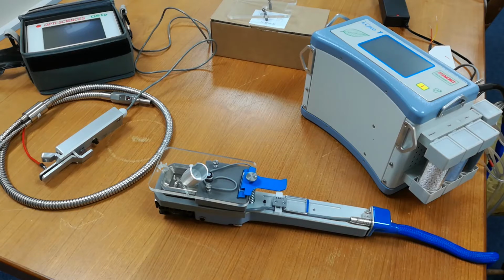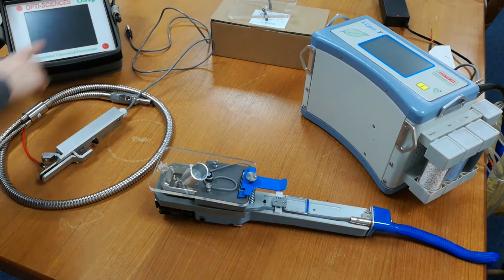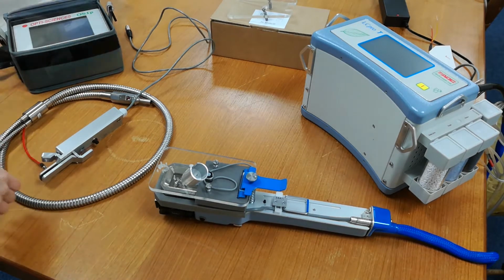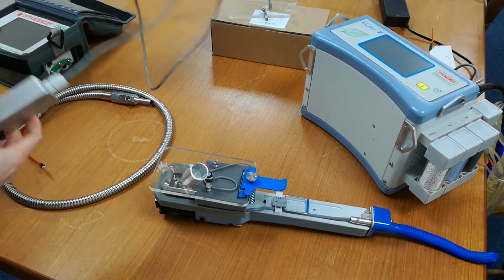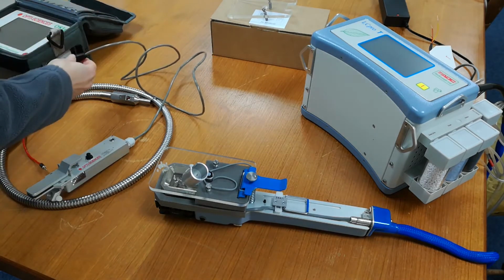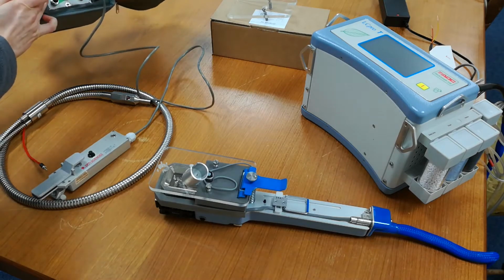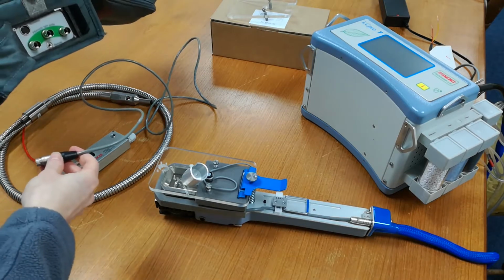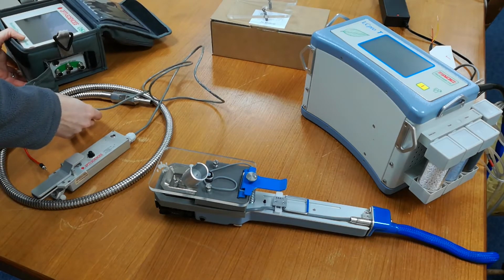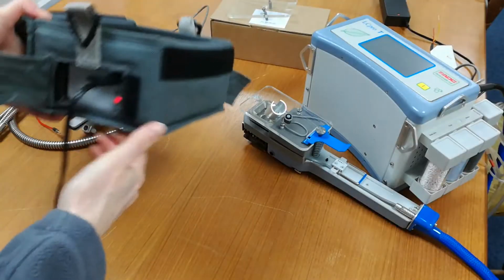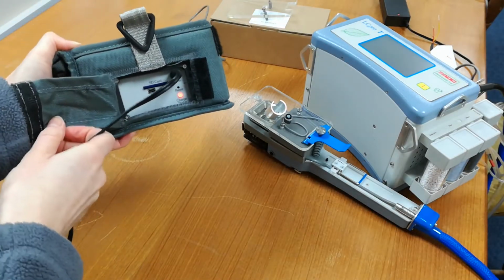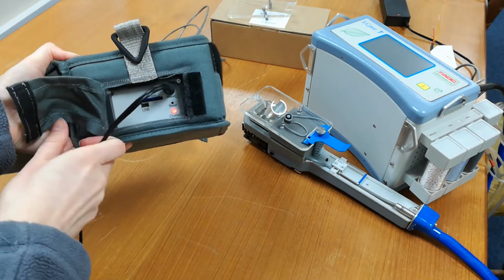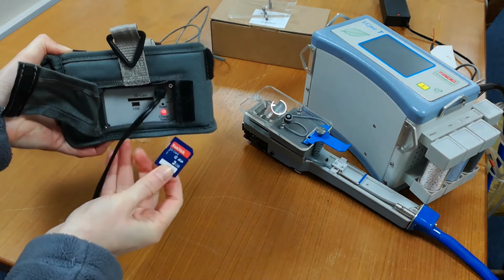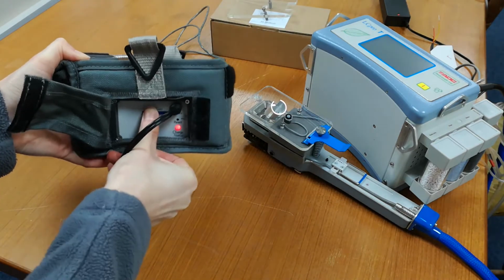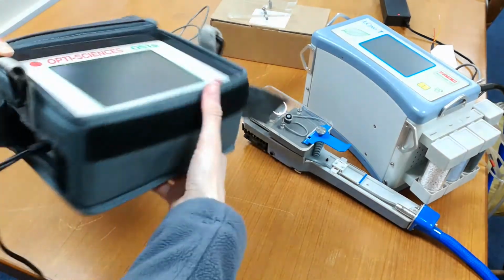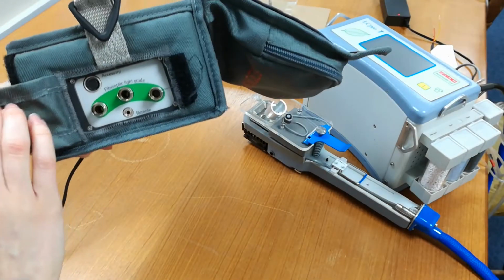Take your OS5p Plus, or in this example, OS1p. OS5p Plus is supplied with its own leaf clip for taking light adapted fluorescence measurements. This leaf clip is not needed when using OS5p Plus or OS1p with the LCpro T. Insert the power cable to charge the fluorometer and insert the SD card into the slot. If you are using the leaf clip supplied with the fluorometer, it fits into the port labelled accessory here.